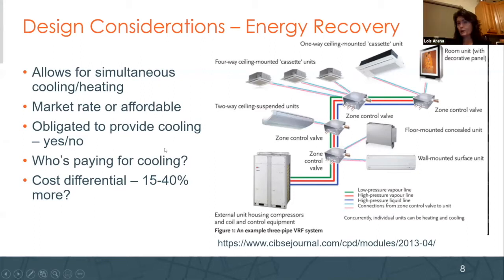Is it market rate or affordable? If it's market rate, you're probably going to put more money into the building. If it's affordable, you've got to be more careful of your budget. Are you obligated to provide cooling? Yes or no? If you are obligated, then you probably want to go with a heat recovery system. If you are not obligated, a heat pump system might be right for you. And you can just say to people, if it's warm in here, open your windows, right? That's not in your contract. Who's paying for cooling? Is it the owner? Is it the occupant? That also is a question of whether or not you should put this in.